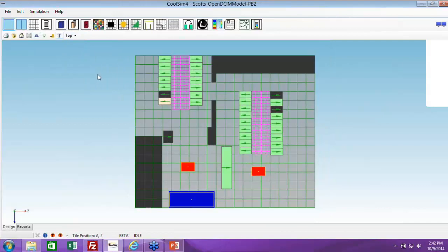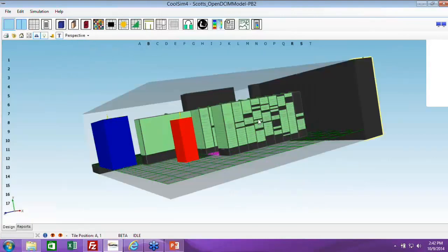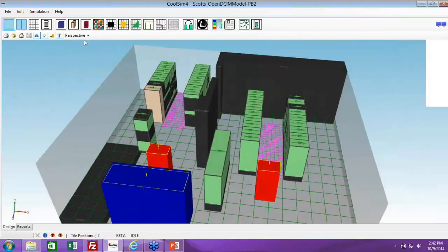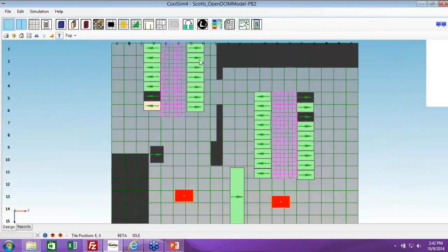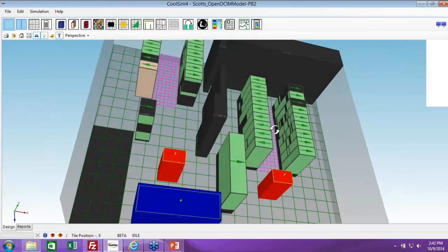And you saw as the data is being read in, we're really getting information about the thermal components. These pieces like blocking and wall representations and the size of the underfloor were added by me. And in a brief discussion before we get started today, I asked him if this looked like his data center, and he said yes, except we have cold aisle containment over here. Again, cold aisle containment, not something that you would have in a DCIM system.